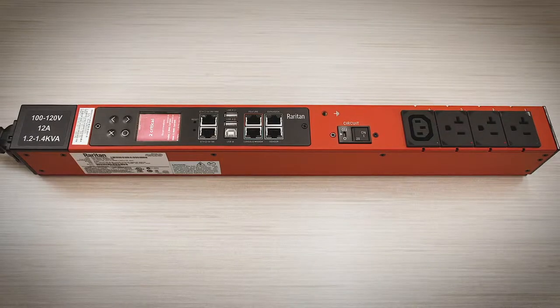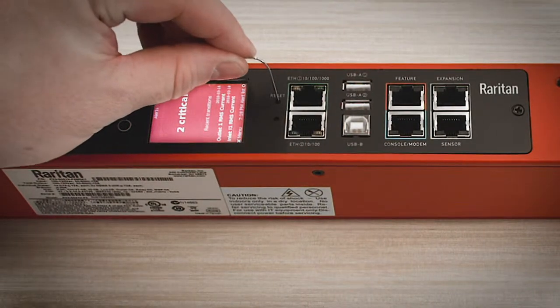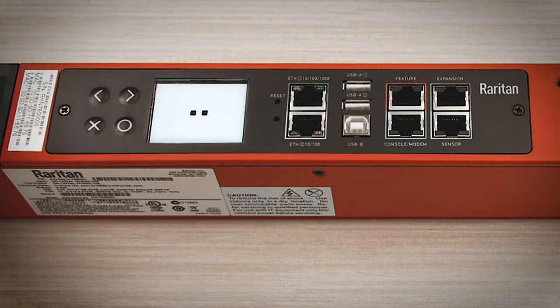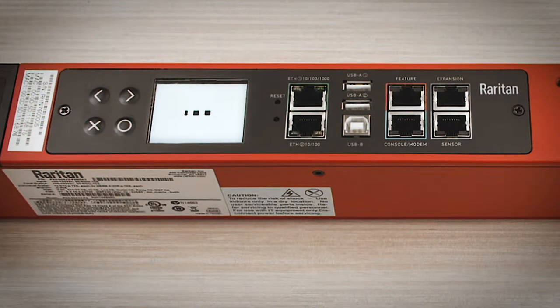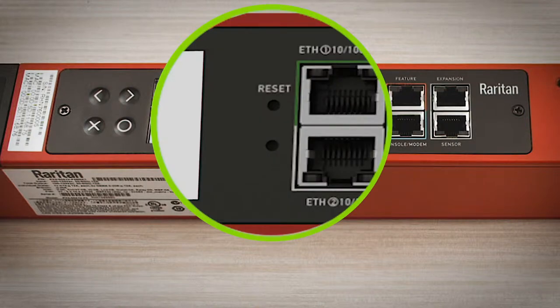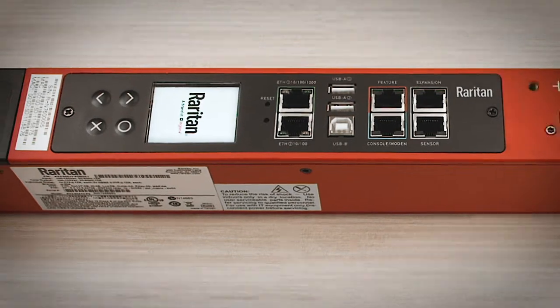The simplest way to reset a controller is with the pinhole reset button. This is common on many types of electronics. The reset button is located inside the small pinhole near the display panel on the PDU, clearly marked reset. Pressing this button is the quickest way to reset the controller without any loss of power to the outlets.